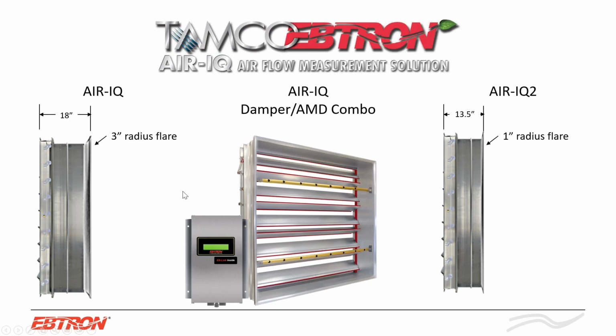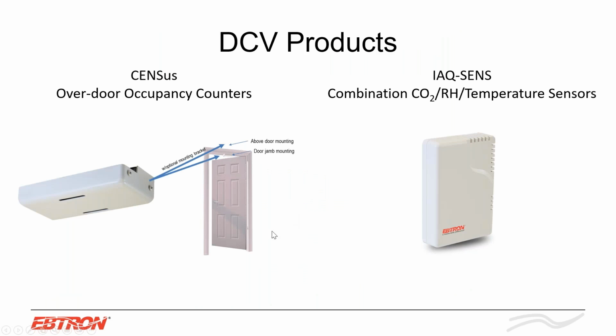We also have damper flow meter combinations, all in one easy package to use with a really high quality Tamco damper. We have the AirIQ, the AirIQ2, outside air intakes, unducted returns, for example, for the AirIQ. So we do have that partnership with them. When I was talking about stack effect, this is a potential solution for this, measuring on each floor or each zone level with this type of flow meter damper combination.